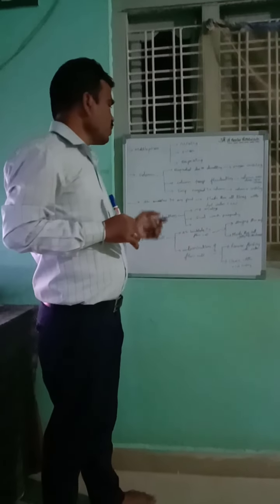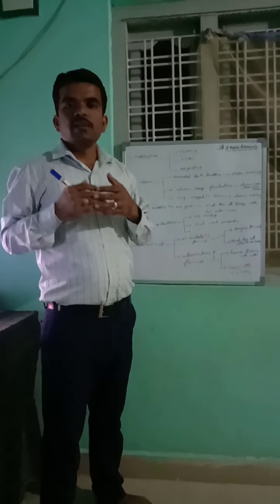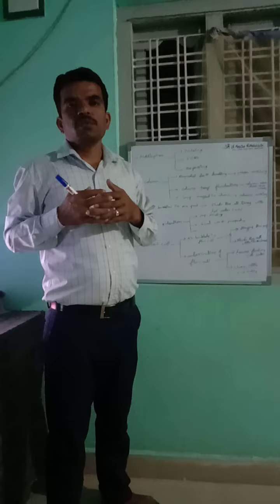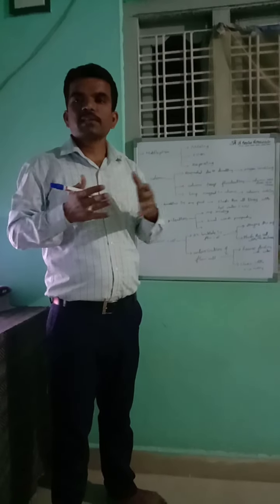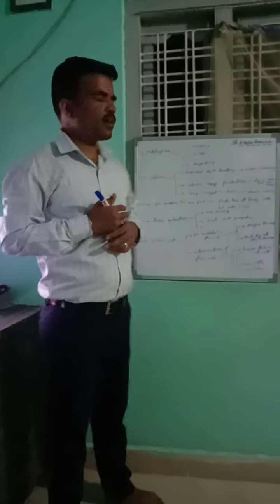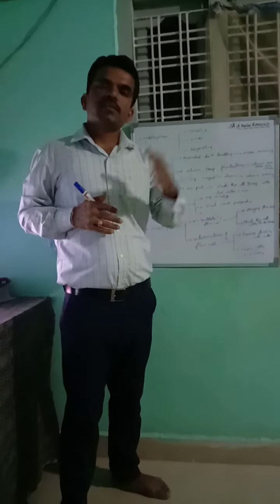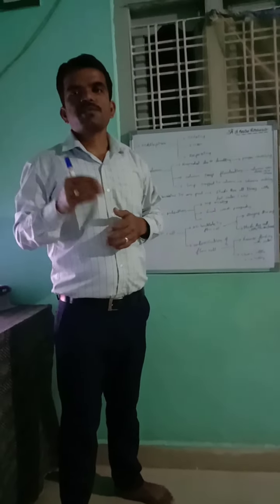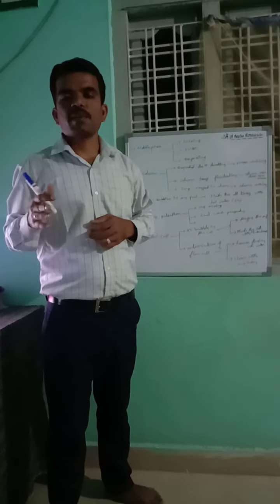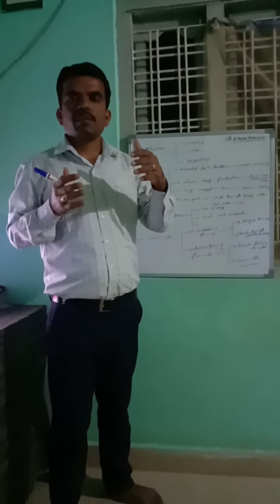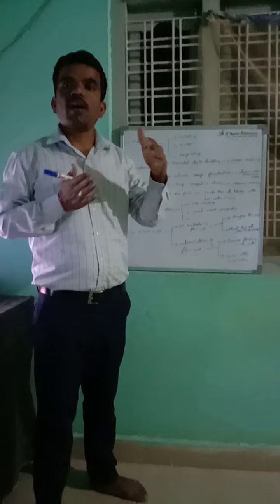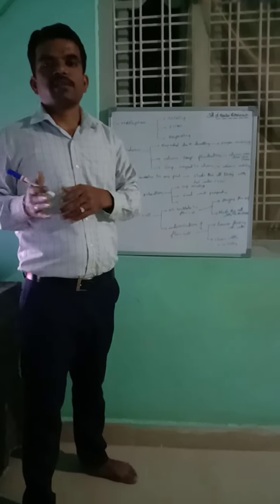And one more: air bubbles trapped in lines. Due to that also we will get some baseline disturbance in our analysis. For that purpose, we have to flush all the lines with hot water. Each port we have to flush for 5 minutes. It is very helpful to remove all the air bubbles in all lines.